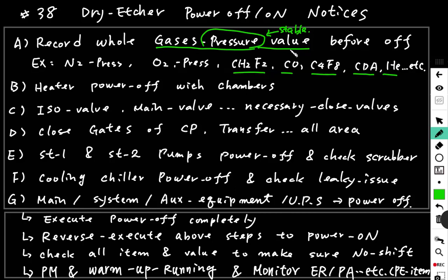After overhaul of the factory, we can compare with this recorded value to make sure the factory gas supply rate is the same as usual. Step B, heater power off. The chamber's heater power off. It needs time to get the temperature down. So power it off to cool the chambers.